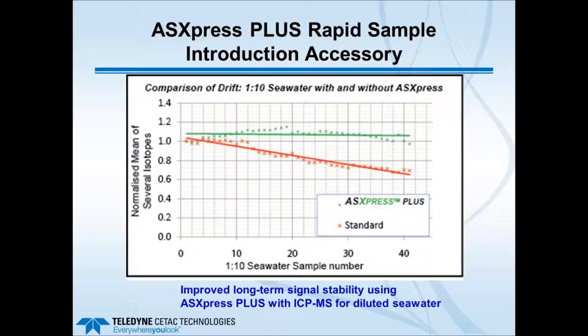One slide I want to mention concerns overall exposure of the sample to the ICP hardware. Work done with diluted seawater comparing the standard nebulizer versus the ASXpress PLUS shows that with the more discrete sampling of the Express Plus, there is much less instrument drift over time. This is due to reduced coating of the ICP torch and sampling cones with salt, since only discrete sample aliquots pass through the loop rather than a continuous stream.